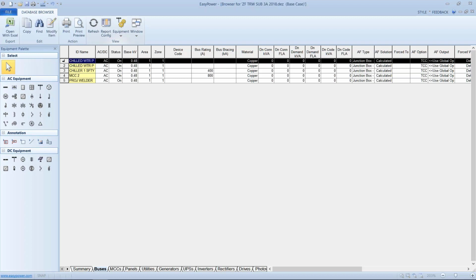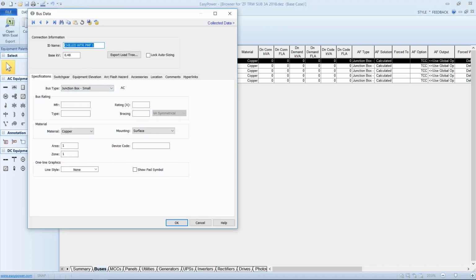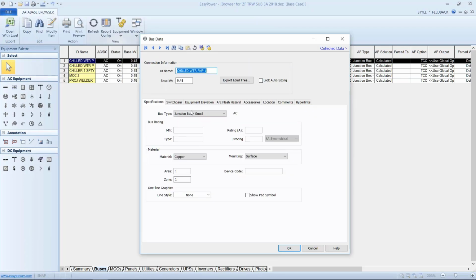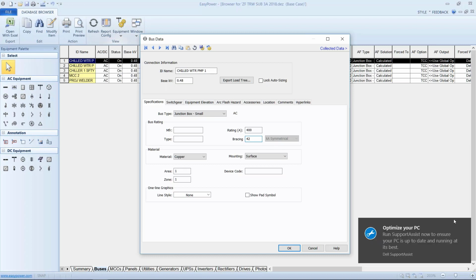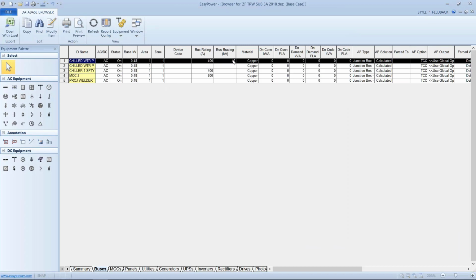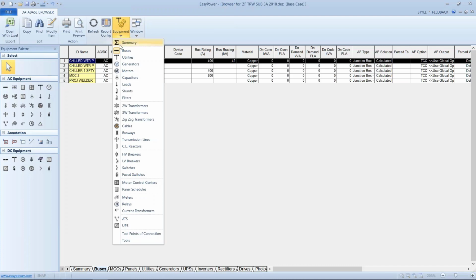Now, I can go through and fix each one of these. For instance, if I open up this chilled water pump, this again is referenced as a small junction box, so I may not care, but in fact, the point I want to make is, even if this is a 400 amp bus and it's rated for 42,000 amps, I really do want to have this in my database, because these numbers will be used for the equipment duty calculation. The other thing I want to look at next is going to be my protective devices.